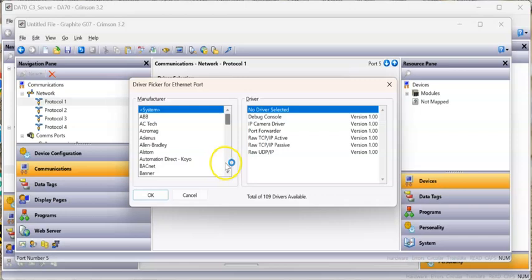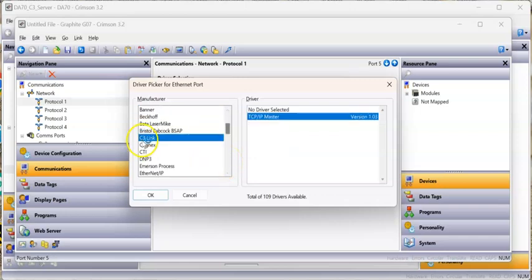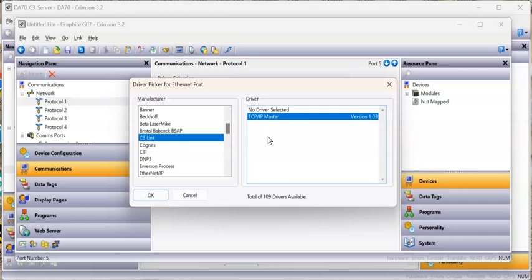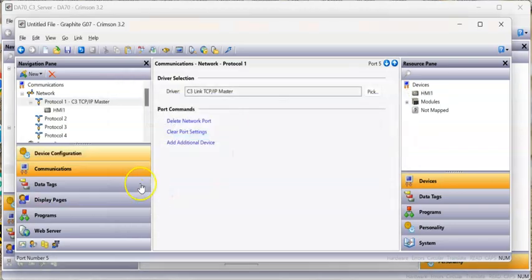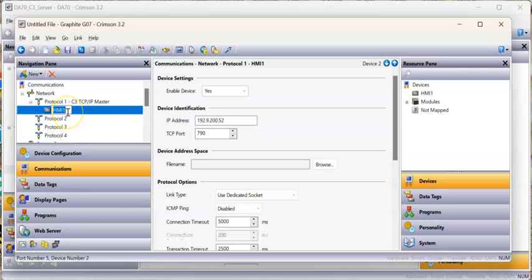In this case, I'm going to go down to C3 Link right here. I'm going to pick C3 Link. So the HMI is going to be the master or client, and the DA70 is the slave or server. I'll click OK. Now you can see this HMI1, I'm going to rename this right now. I'll call it DA70_222.